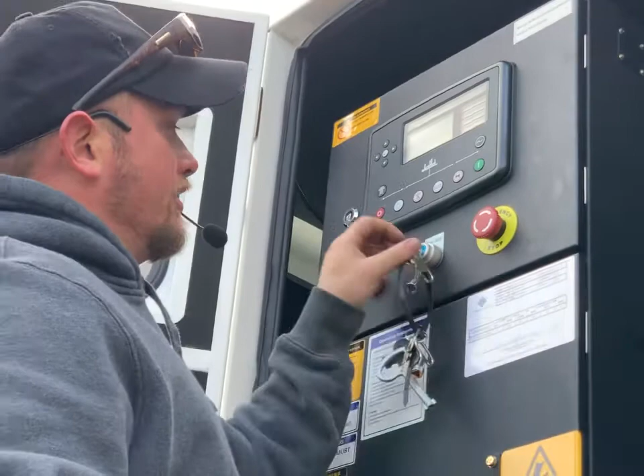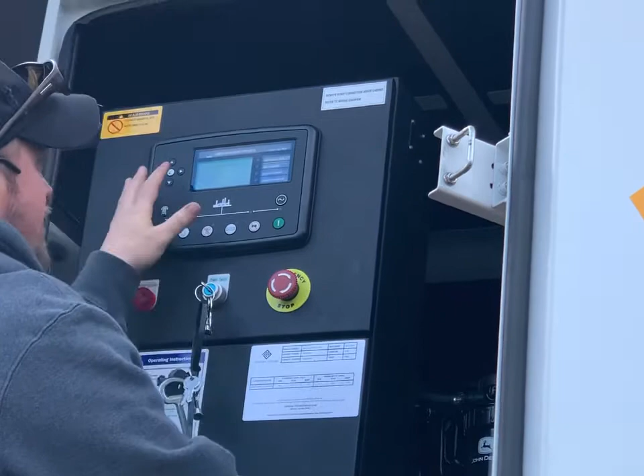We've checked the oil and checked the coolant, both are at the appropriate level they need to be. We turn the main supply on for the battery, and come over to our Deep Sea Electronics controller and turn the key on. That gives you a display on the screen up here, and it'll tell you that the generator's at rest.